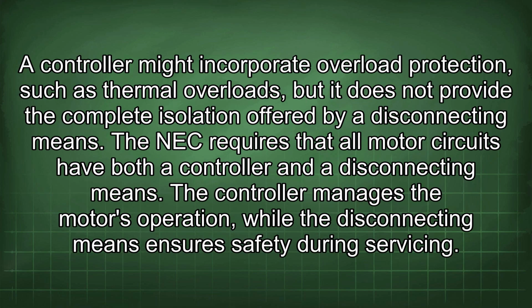A controller might incorporate overload protection, such as thermal overloads, but it does not provide the complete isolation offered by a disconnecting means. The NEC requires that all motor circuits have both a controller and a disconnecting means. The controller manages the motor's operation, while the disconnecting means ensures safety during servicing.